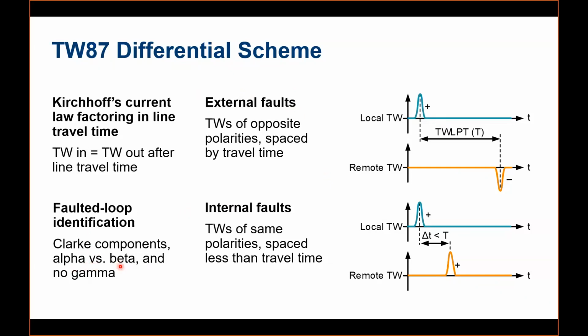Similarly, for internal faults, we use some Clarke transformation parameters like the alpha and beta components of the three-phase currents. And the principle is very simple. If a traveling wave is created by an internal fault, the local end will see it with one polarity and the remote end will see it with the same polarity, just because of your CT configurations of the start points. And the time between both the relays, the time of interception of these traveling waves, will be less than the line propagation delay, because you can just consider a feeder and the fault maybe in the middle. So the traveling wave will definitely take less time than the total TWLPT time to reach both of the ends.